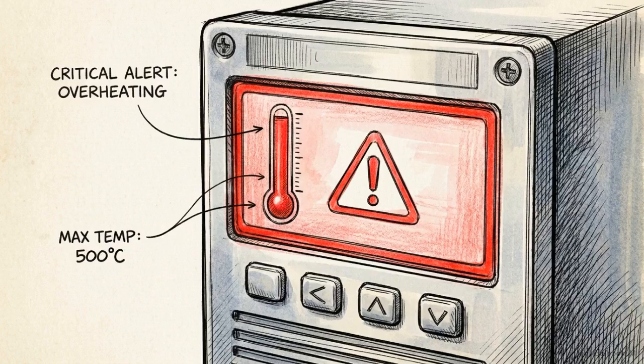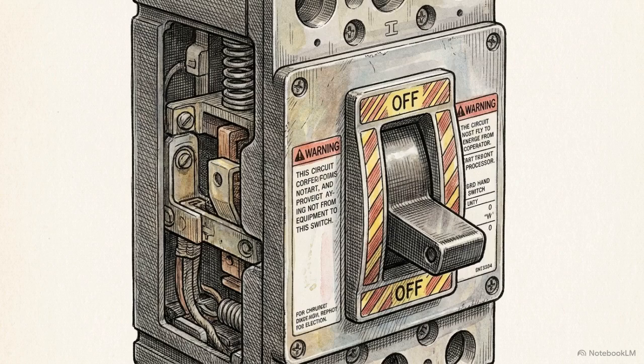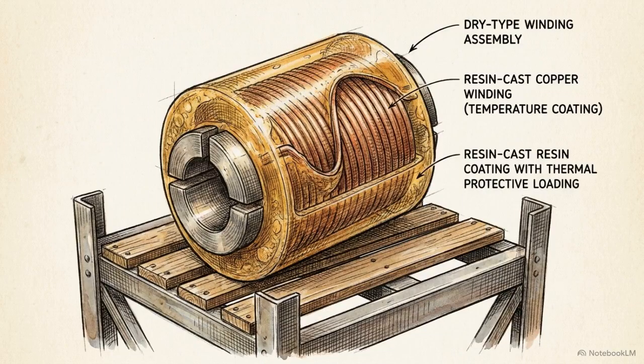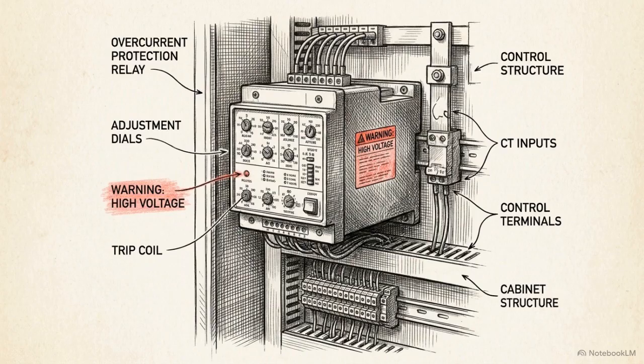Then, we set the critical WTI trip limit at 90 to 95 degrees Celsius. This is the absolute ceiling. If the coils hit this temperature, the relay forces a breaker trip to shut the system down. Configuring these strict limits provides our first line of defense against irreversible thermal damage to the winding insulation. With our thermal limit secured, we move to our second line of defense, mitigating electrical threats, specifically phase-to-phase faults, using overcurrent protection.